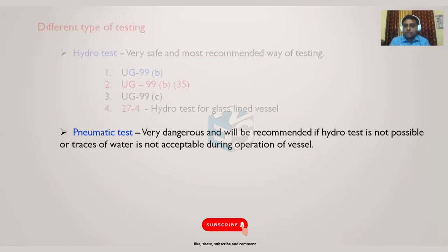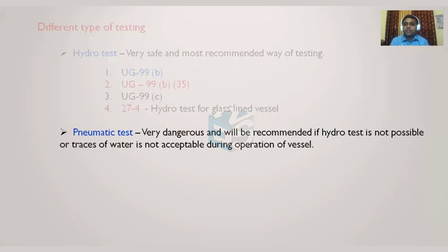For example, in a refrigeration plant, water mixed with ammonia can be a very dangerous situation, so water traces must not remain. Vessels in refrigeration systems are pneumatically tested. If hydro testing is performed, the vessel should be thoroughly dried using a dryer, with no traces of water remaining.